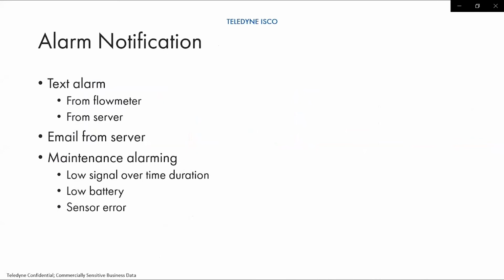And so you can send maintenance alarms based off of low signal over a duration of time. So again, we don't want to look at instantaneous readings. So if we see that I've got signal strength at 30% for 1 hour or more, then that would be my trigger to send somebody out.